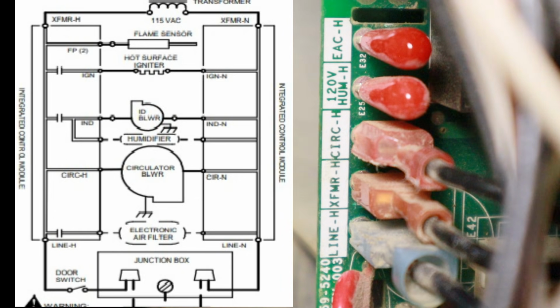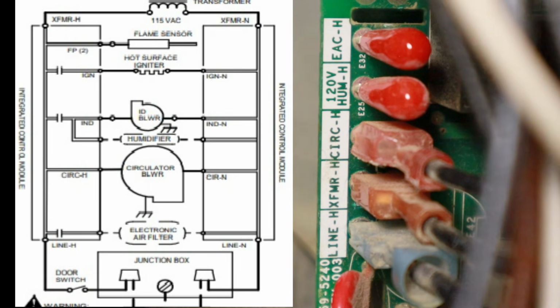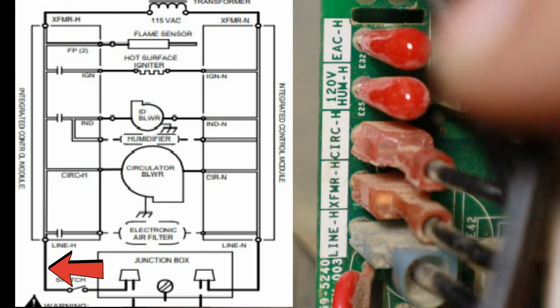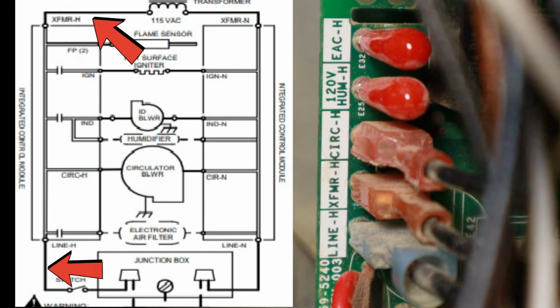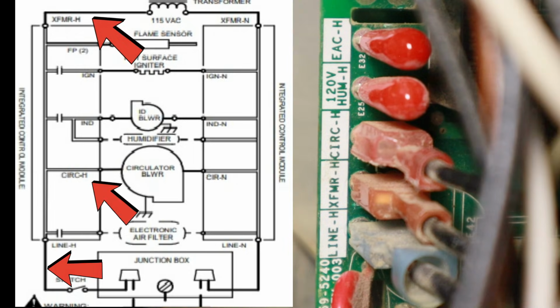So what we're figuring out here is where we always have live power no matter what state the unit is in. Even when it's in idle, sitting by, it's not cooling, it's not heating, we always have power on those terminals because we now can look at the schematic and see where we should have power at all times. So now we know two things. We have power coming in on our line H, we have power going to our transformer, and we have power going to our blower motor.